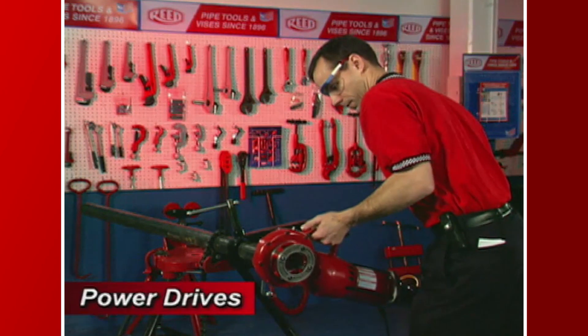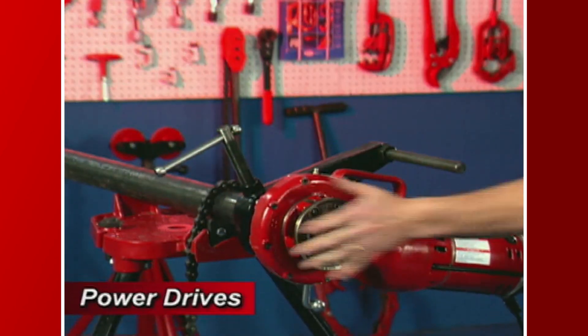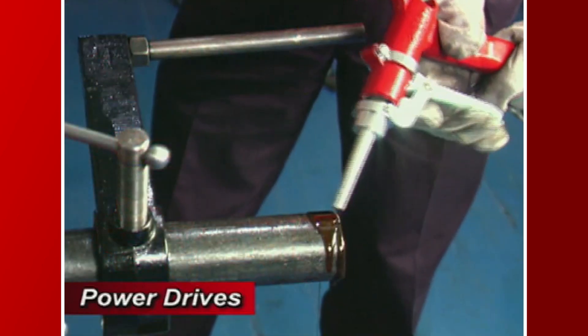Continue by placing the die head over the end of the pipe, making sure the power drive is correctly positioned under the support arm. Liberally lubricate the general area to be threaded with thread guard cutting oil. For right-hand threads, the die should rotate clockwise when looking at the face of the die head.